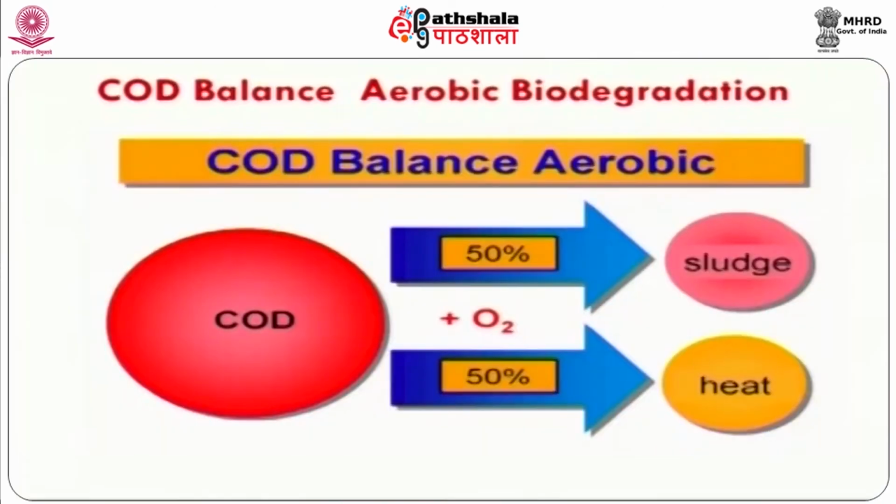The reaction is very rapid in nature. So, we have to provide all essential nutrients to support bacterial life. If we consider aerobic activity, aerobic bacteria require carbon, nitrogen as well as phosphorus in the ratio of 100:5:1.